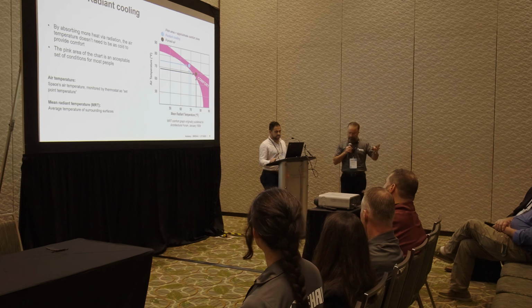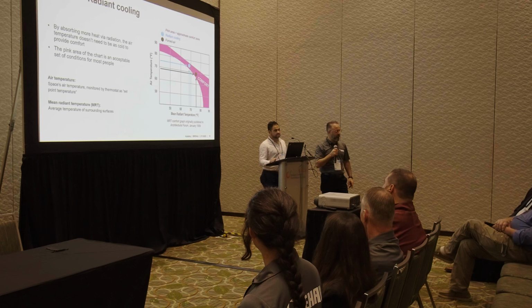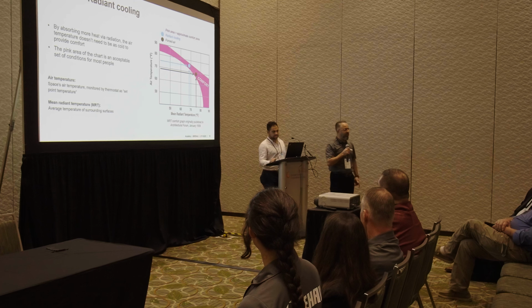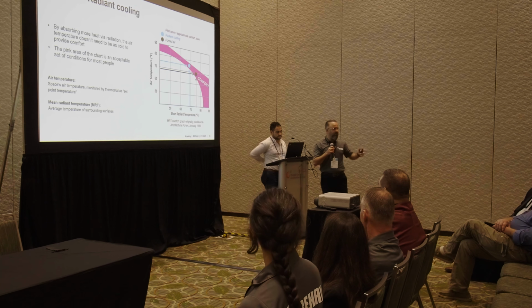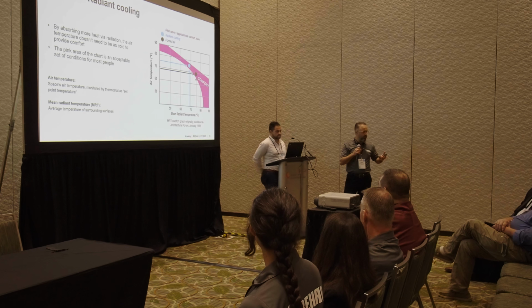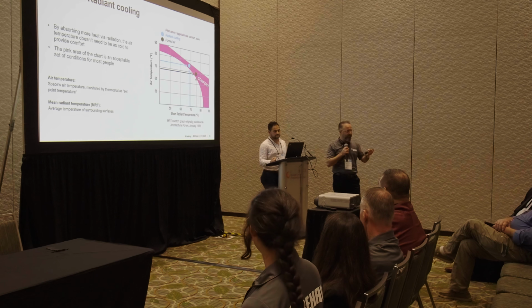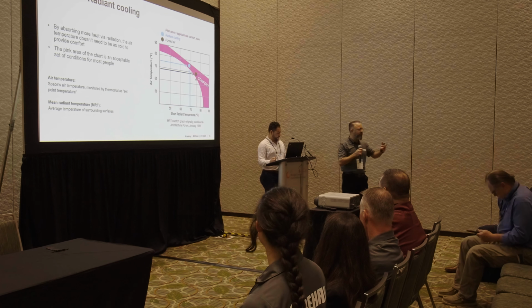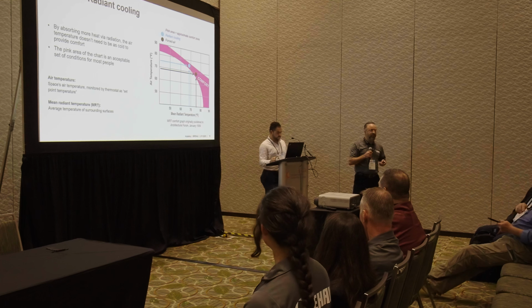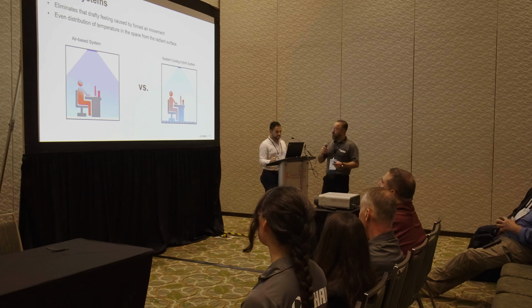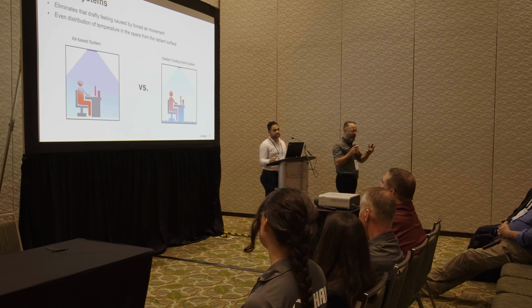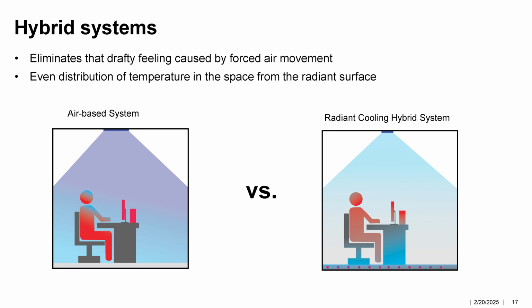I don't know if you guys have fan coils in your bedroom, in your, let's say, dining room. What's the setting that you put it on on a regular summer day? My point is, if you normally try to be in a comfortable zone around 74, 75, you can leverage it a little bit higher. So you're using the radiation of your body towards surfaces, and letting the air inside be a little bit more than usual. And that's what we call the corrected thermal profile. And using that, you can minimize your air system.